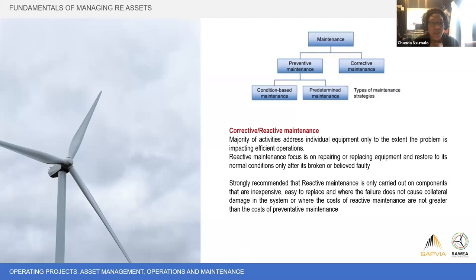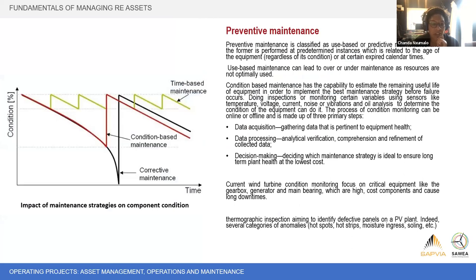And you can do this in a couple of ways. So see here, condition-based maintenance and predetermined maintenance. Condition-based maintenance requires you to have quite a lot of finger on the pulse of the data and the activities that are happening on your site. So tracking all of that and analysis of how equipment is operating, but worth putting in place from the beginning of your site operating so that you're building up a database of failures and failure rates and how your equipment behaves. Kim, I think then what you'll see is a bit more detail on all of this as we go through.